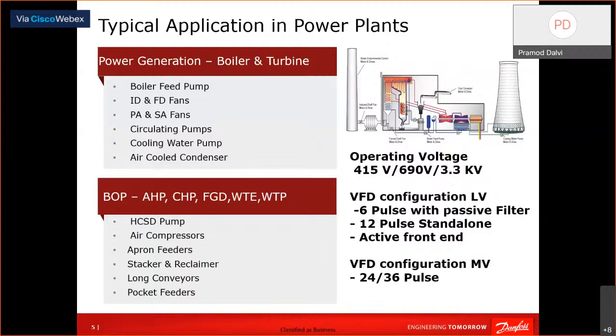For the operating voltage, we see 415 or 690 V, or sometimes it goes to 3.3 or 6.6 kV, based on the power rating of the motor. In low voltage, we work with 6 pulse, 12 pulse, and active front end configurations, based on the harmonics and the power rating. We define this configuration, and if there is a consultant, then we follow the consultant specifications. For medium or high voltage, it is either 24 or 36 pulse.